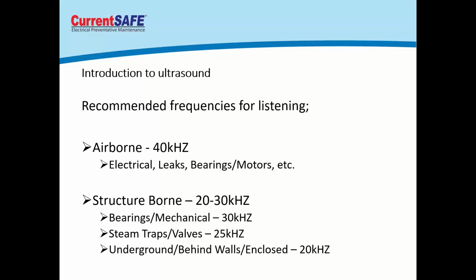That said, everybody's hearing is a little different—everyone hears a slightly different frequency range—so you can adjust up or down a frequency or two, say 39, 41, or 42, to better tune to your hearing and how your brain processes those airborne signals. But airborne is typically around 40. Structure-borne is usually 20 to 30, and bearings, mechanical equipment, steam traps, underground or behind-wall applications all have different associated frequencies.